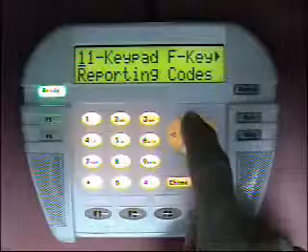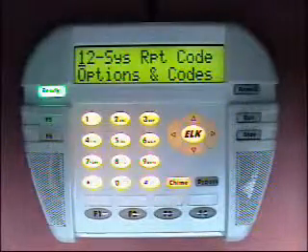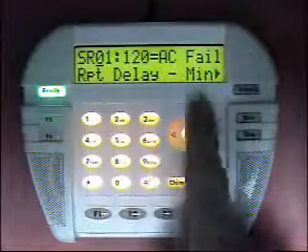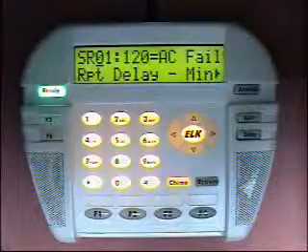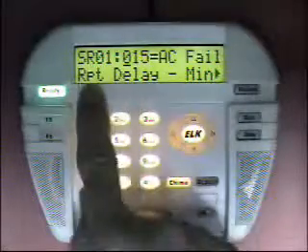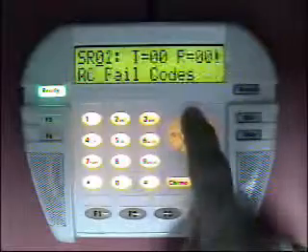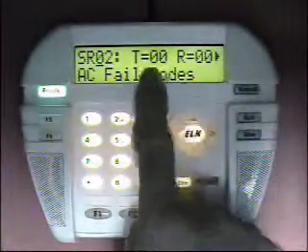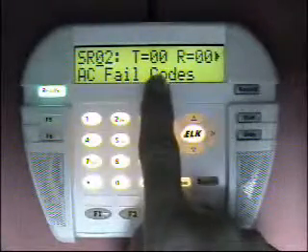We'll back out and move to Menu 12: system report codes, options and codes. The first option is the AC fail report delay time in minutes — the amount of time that will elapse before an AC failure is reported to the central station. It's set for 120 minutes; to change to 15 minutes, enter 015. The next option is the AC fail code: T is for trouble and R is for restoral. These must be set to a non-zero value for them to report.